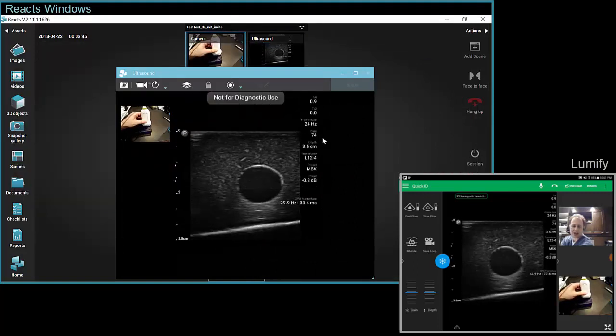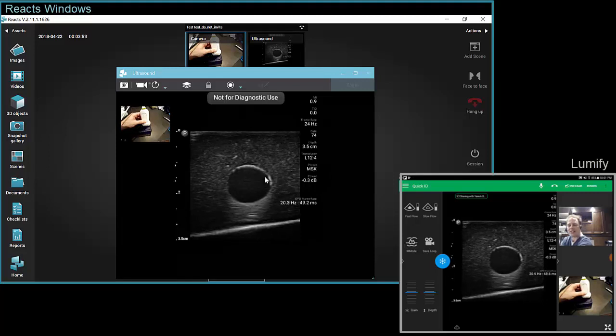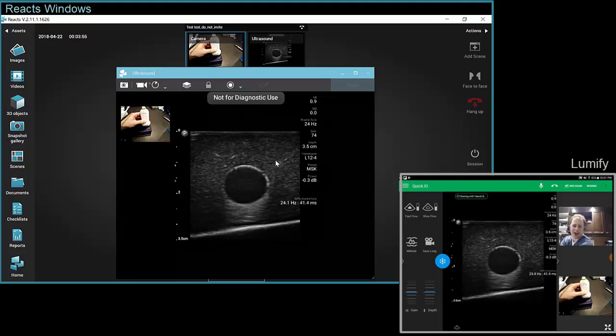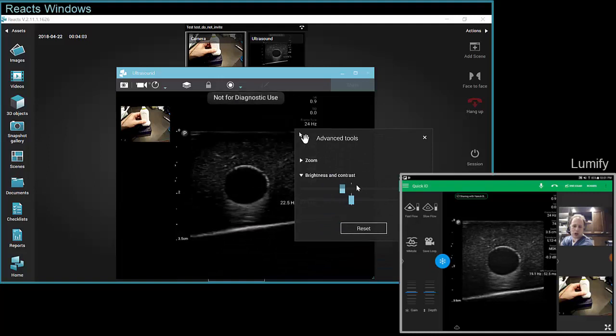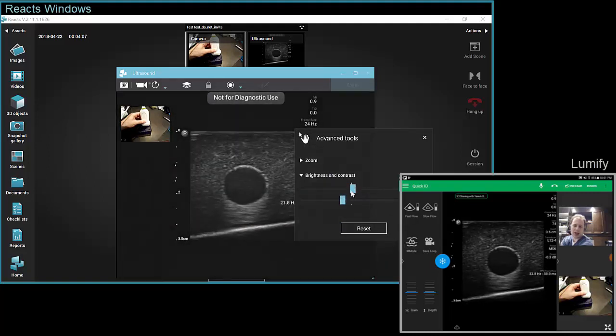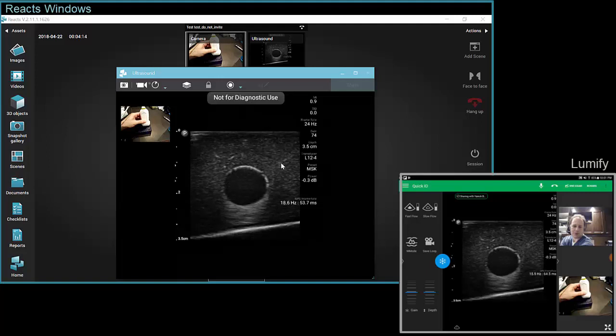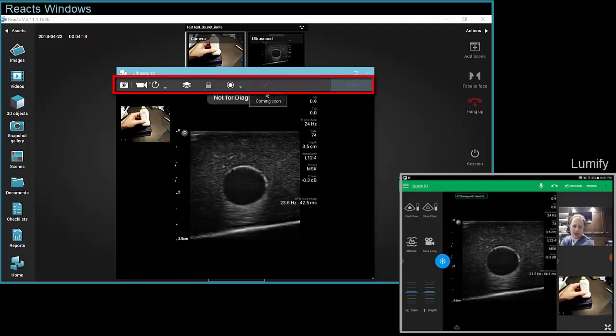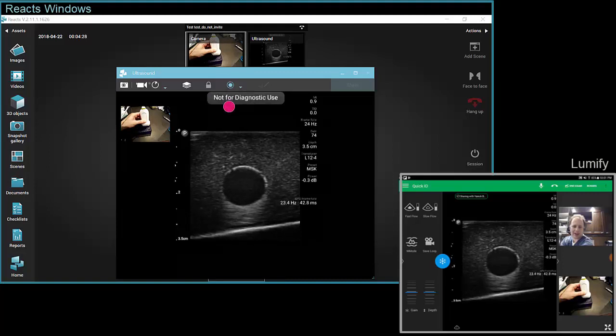Let's focus on the main Reacts scene with the ultrasound stream. If you would like to change the brightness and contrast on your own without asking the Lumify user, you can right-click by placing your mouse on the ultrasound stream and choose brightness and contrast. You can change the brightness and contrast on your side as you want, and if you ever want to go back to the neutral default, just click reset. An important button in the menu bar of the scene is the pointer — the wide circle.